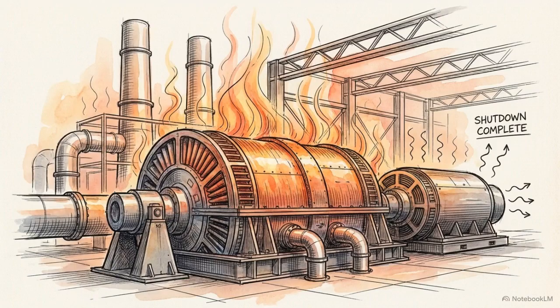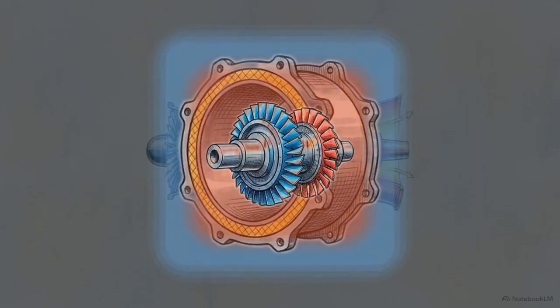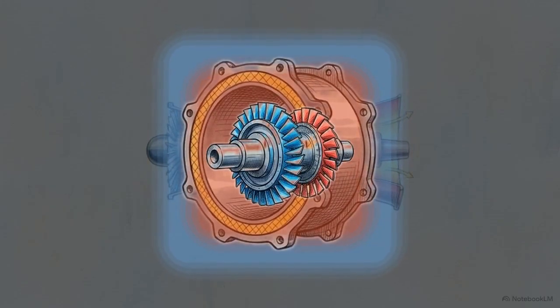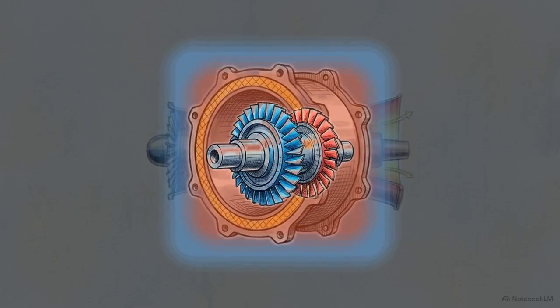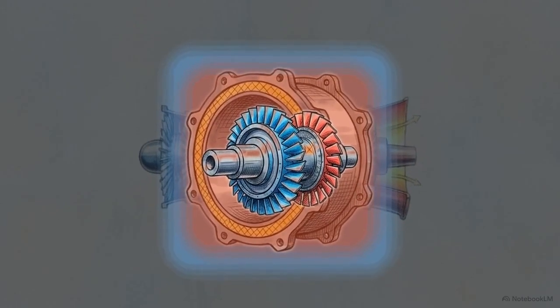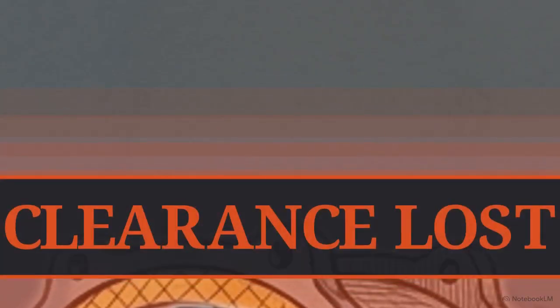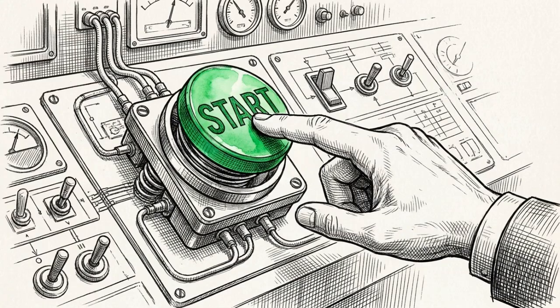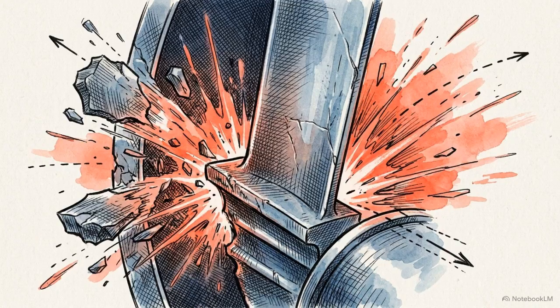A turbine is in its most mechanically vulnerable state in the minutes immediately following a high-power shutdown. This cross-section shows a thermal mismatch. The thin outer casing loses heat quickly and begins to shrink. The massive, dense rotor spinning inside retains its heat and its physical expansion much longer. As the casing cools and constricts, it shrinks around the still expanded rotor. The clearance between the turbine blade tips and the casing wall effectively disappears. If an operator attempts to restart the engine during this window, the centrifugal force will grind the expanded rotor blades directly into the shrunken casing, causing a catastrophic rotor rub.